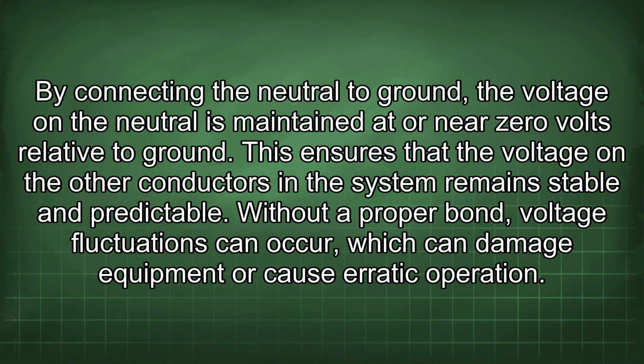Thirdly, the bonding provides a stable reference point for the electrical system. By connecting the neutral to ground, the voltage on the neutral is maintained at or near 0 volts relative to ground. This ensures that the voltage on the other conductors in the system remains stable and predictable. Without a proper bond, voltage fluctuations can occur, which can damage equipment or cause erratic operation.